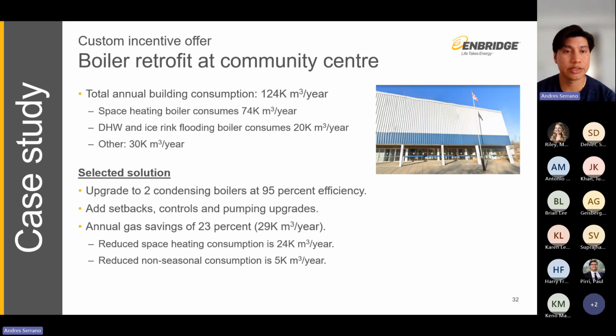The building consumed approximately 124,000 cubic meters per year. Through our energy modeling, we've estimated that space heating consumes 74,000, domestic hot water and ice rink flooding consumes 20,000, and the makeup air and rooftop unit consumed 30,000 cubic meters of natural gas per year.